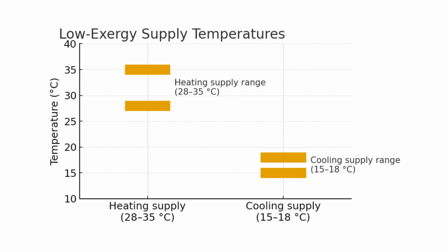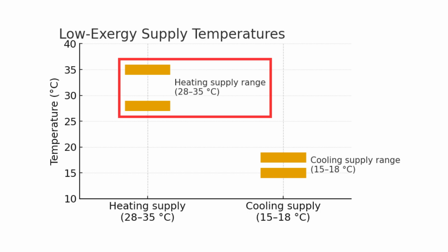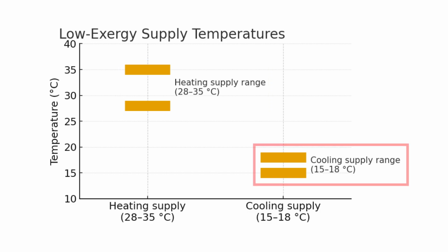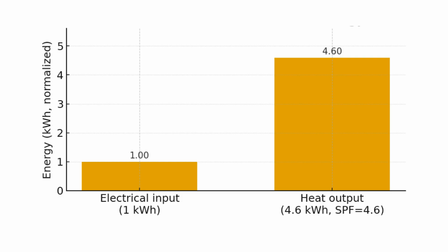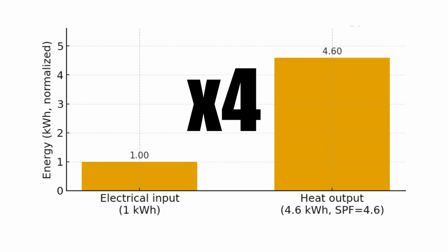This method uses the low exergy principle, working with small temperature differences to minimize energy waste. For heating, supply water only needs to reach about 28 to 35 degrees Celsius. For cooling, just 15 to 18 degrees Celsius is enough. Because the heat pump isn't fighting extreme temperatures, its seasonal performance factor, or SPF, reaches up to 4.6. That means it produces more than 4 times the heat energy compared to the electrical energy it consumes.